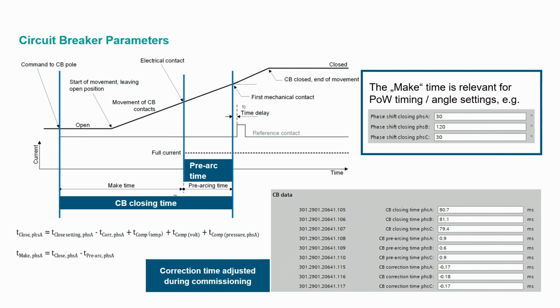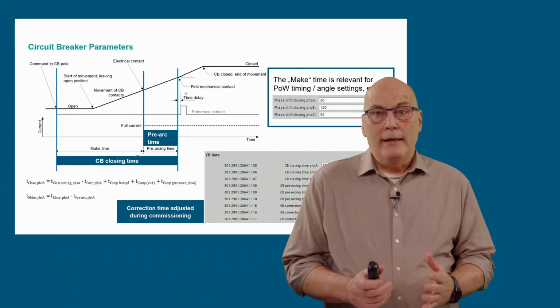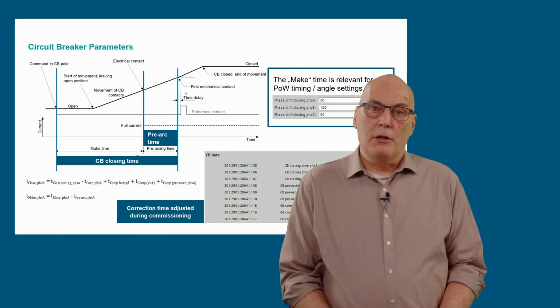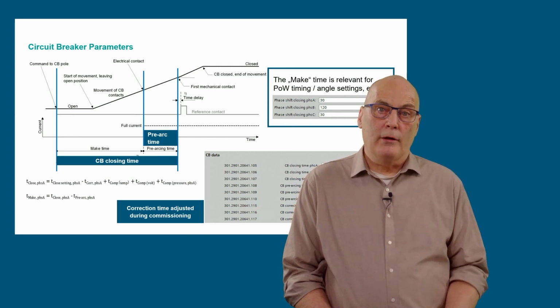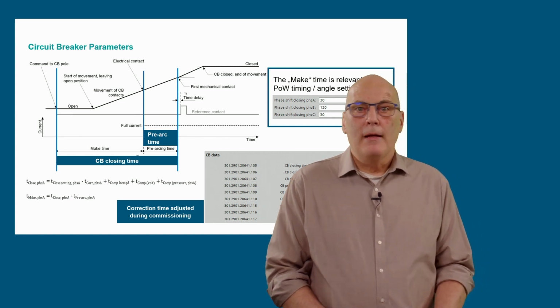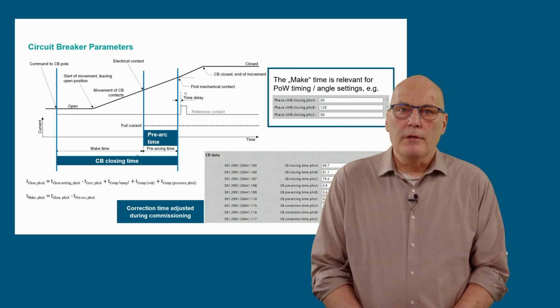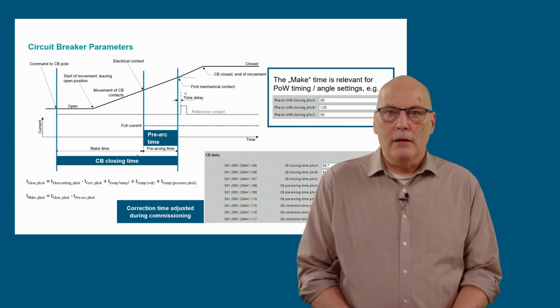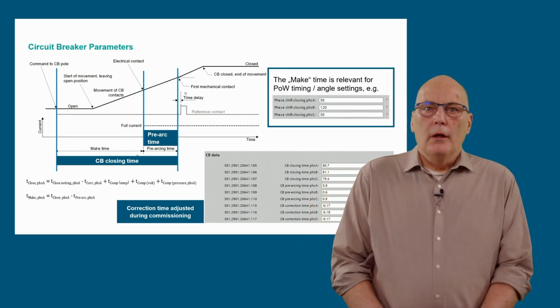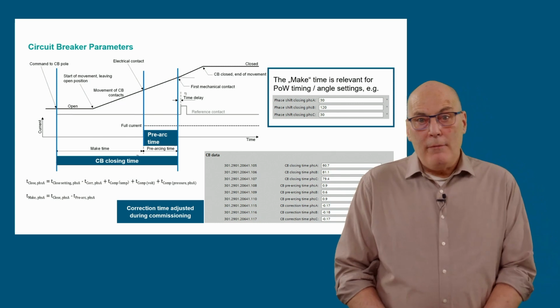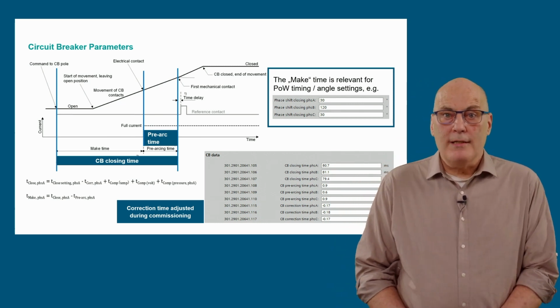The closing time, highlighted in the bar in the middle of the diagram, is the first value that must be set. It can be obtained from the circuit breaker data and is set for each phase as shown. It is the time from initiating the close command by IO209 contact on left of diagram until the primary contacts of the circuit breaker make first mechanical contact. Important, all the other timing values will be calculated starting with this setting.